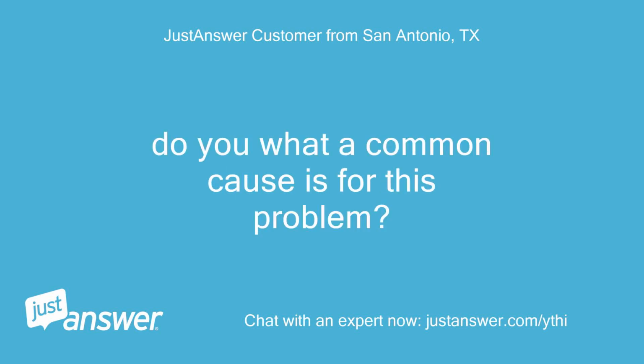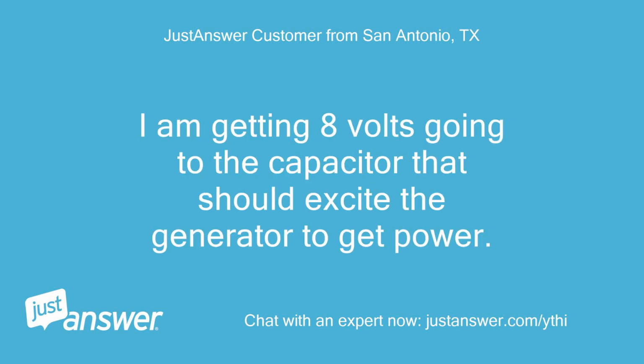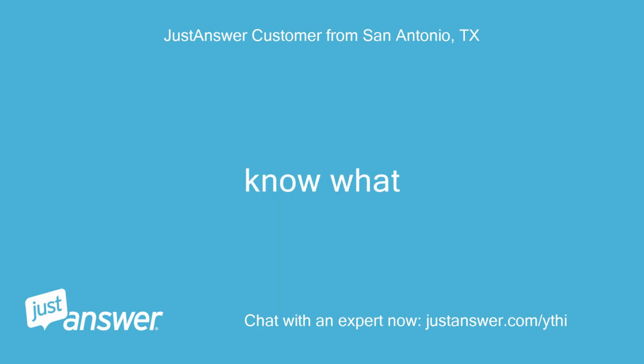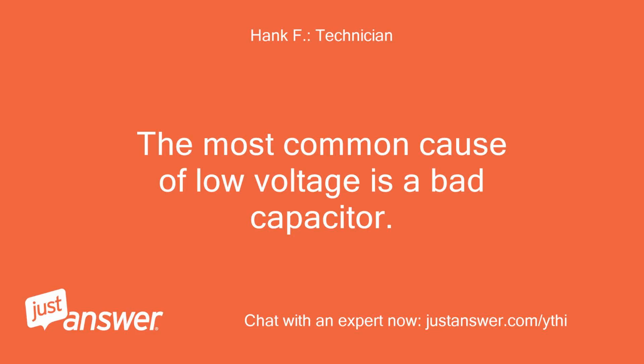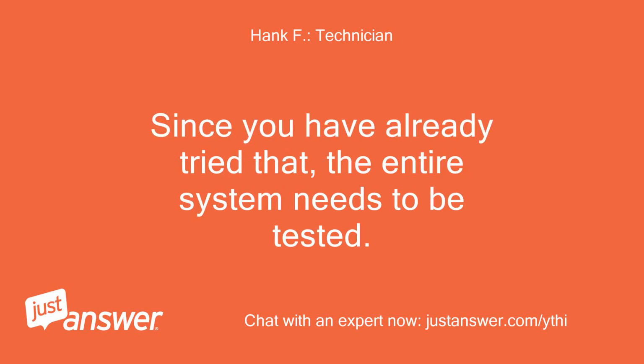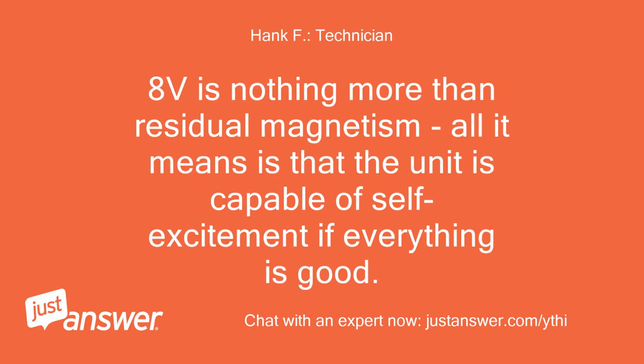Do you know what a common cause is for this problem? I'm getting 8 volts going to the capacitor that should excite the generator to get power. Know what? The most common cause of low voltage is a bad capacitor. Since you have already tried that, the entire system needs to be tested. 8 volts is nothing more than residual magnetism. All it means is that the unit is capable of self-excitement if everything is good.